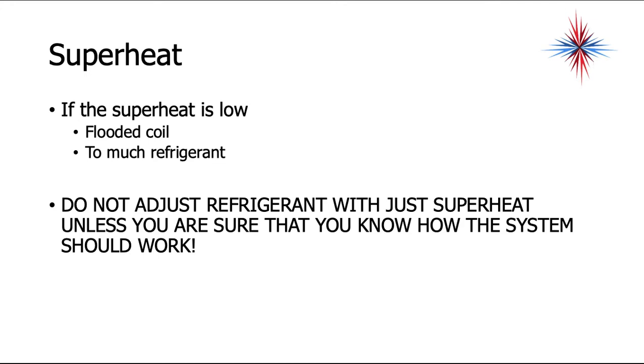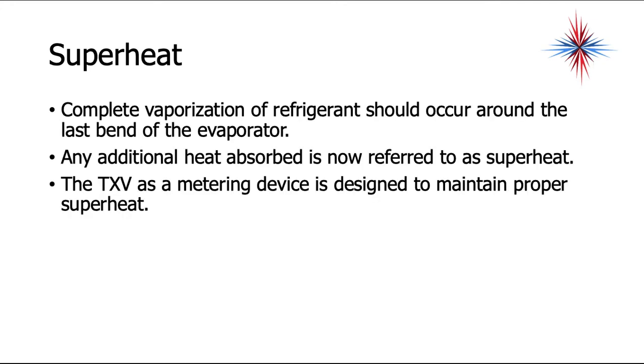Refrigerant is never used up. Once it's charged properly, it should stay in that system forever unless there's a leak. Just adding refrigerant is not the answer to most problems. Complete vaporization of the refrigerant should occur around the last bend of the evaporator. Any additional heat absorbed — that sensible heat — is now referred to as superheat. The TXV as a metering device is designed to maintain proper superheat.